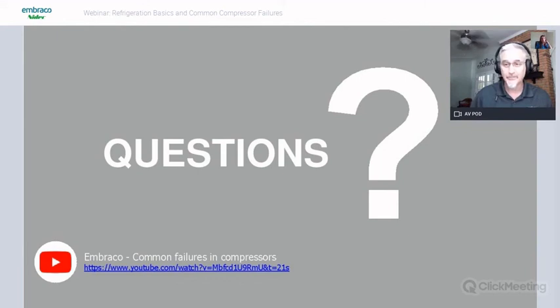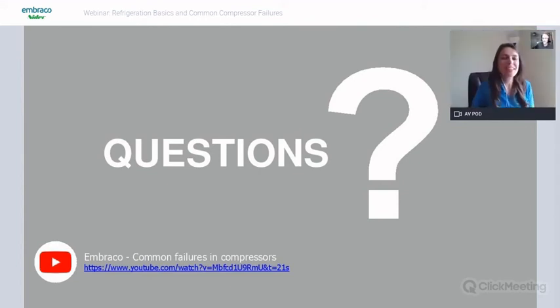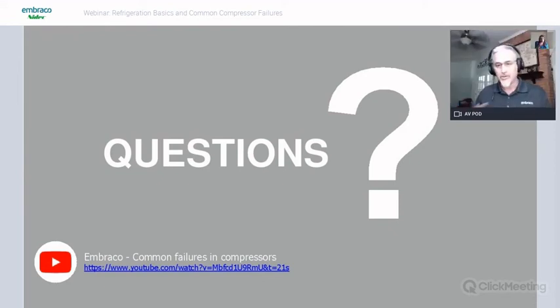Understood. And another question from Neil Hadje. I don't know if I pronounced it correctly. You mentioned damage to the suspension system. Are you saying that if we hear the motor clank against the shell during moving, that the suspension is compromised and the compressor shouldn't be used? So if you're picking the compressor up in your hands and you hear it clank, that's no problem. That's completely normal. That just means you're going beyond the design of that suspension system. You're going to hear that when you move the compressor.